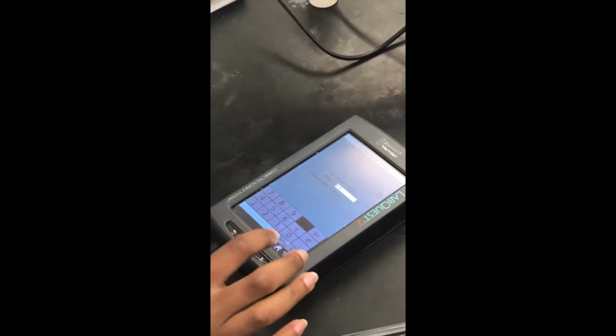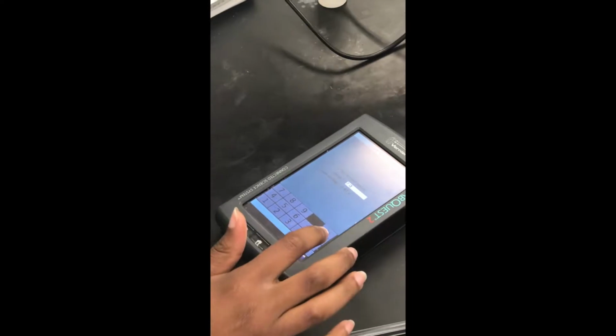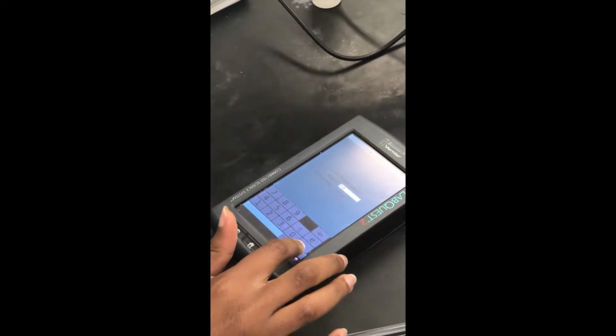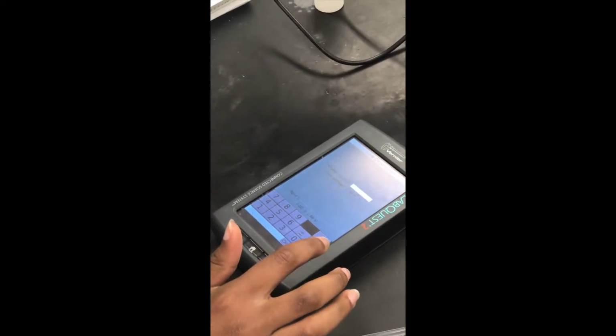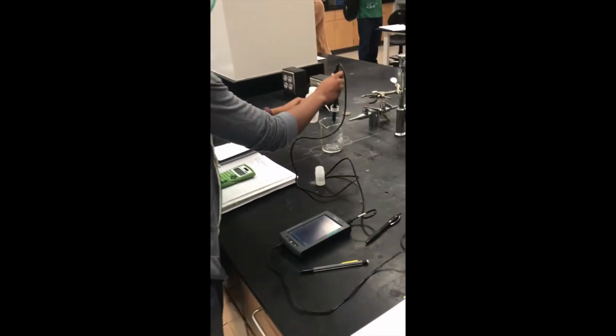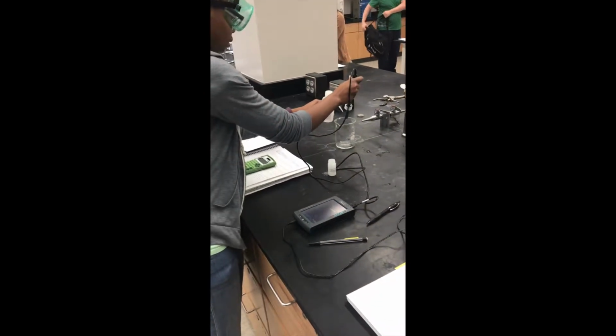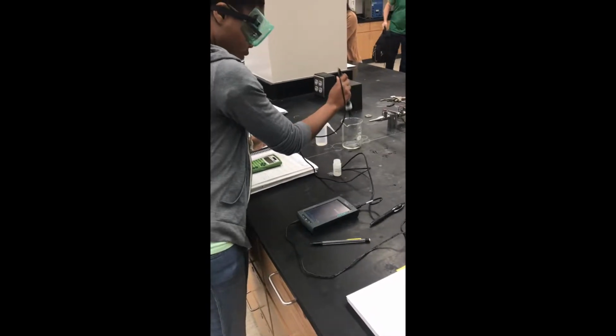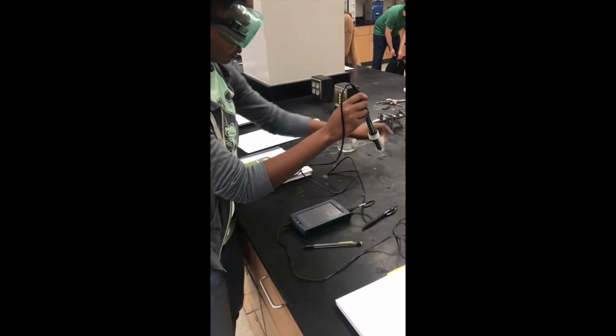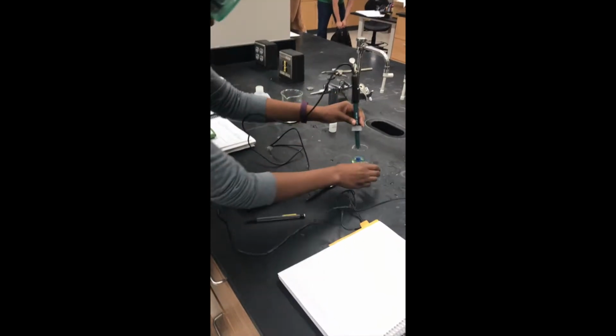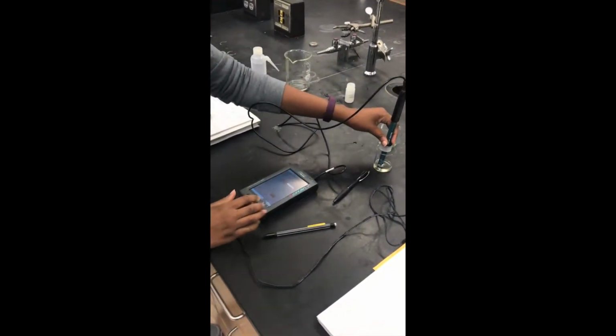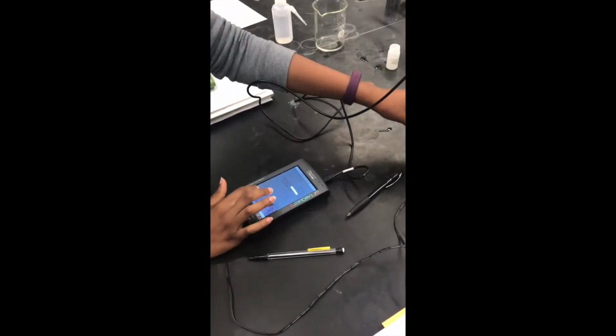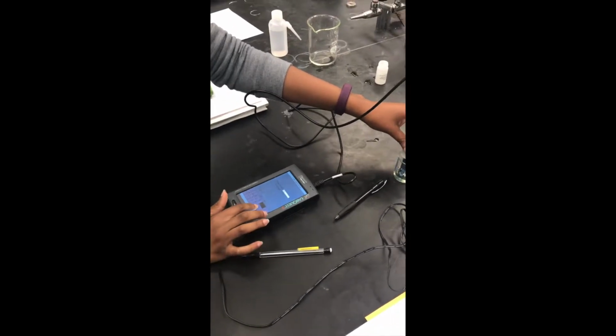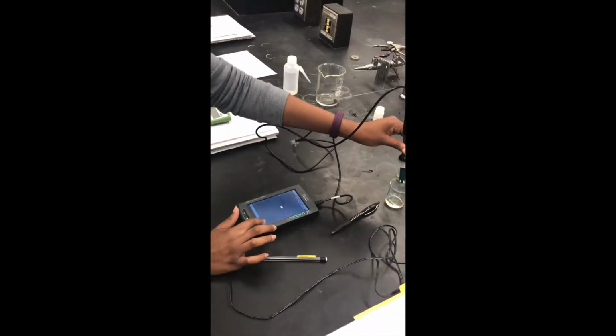We placed the probe in pH buffer 7 first, and after placing the probe in pH buffer 7, we waited for the voltage to stabilize, and then we entered 7 into our pH meter. We kept the data, and after keeping the data, we took the probe out of pH buffer 7 and washed it off with deionized water as well. After washing it off with deionized water, we did the exact same method for pH buffer 4.